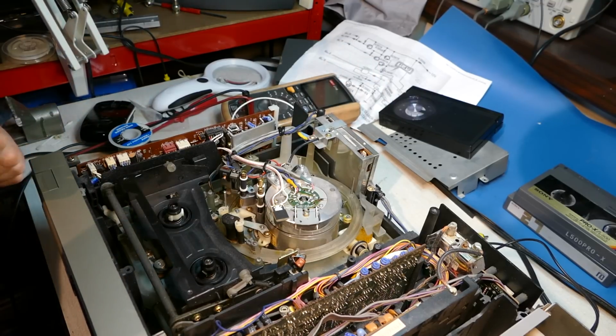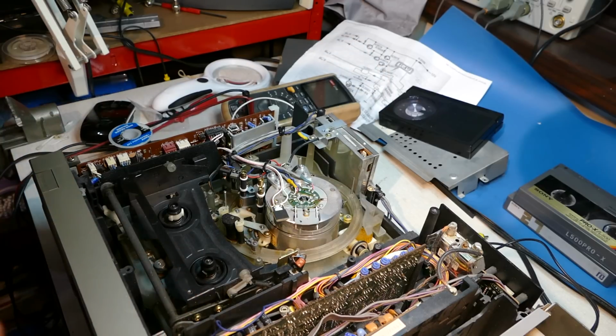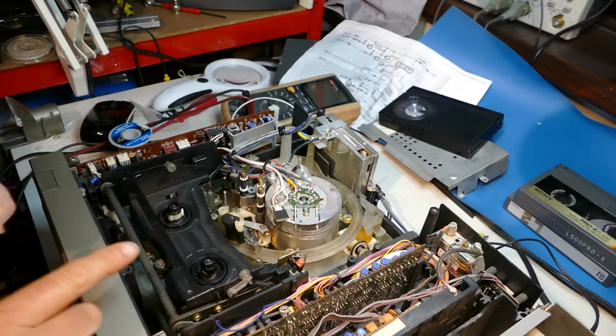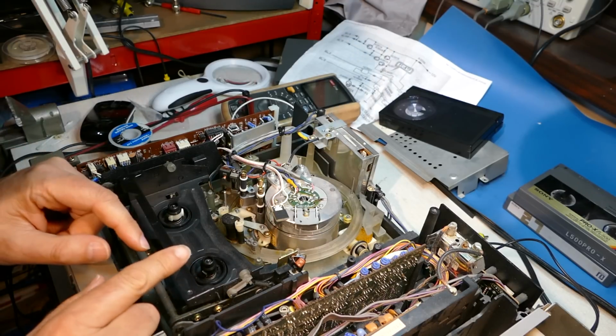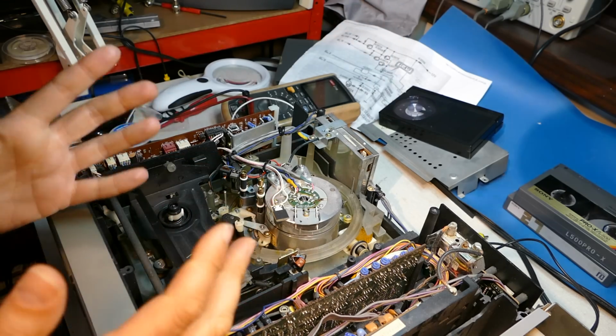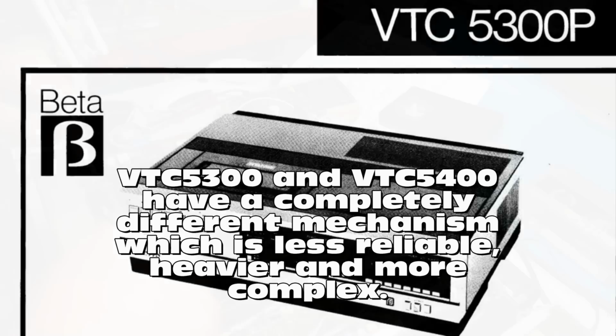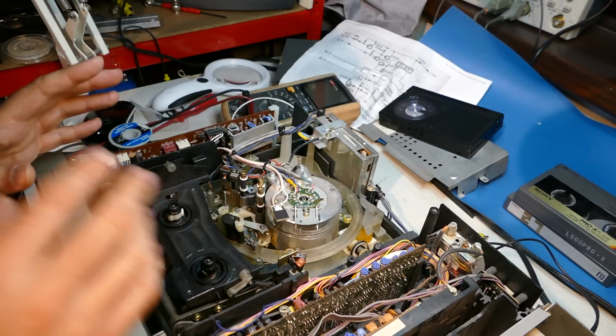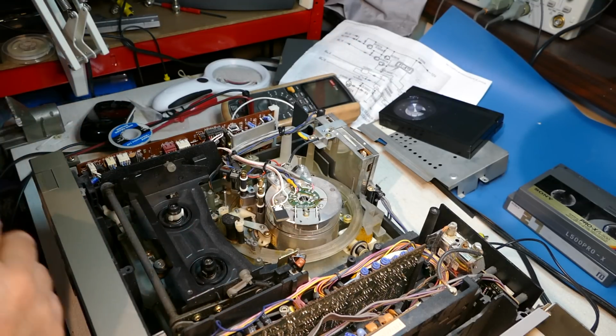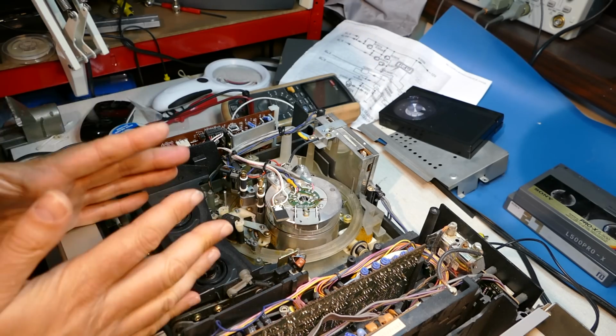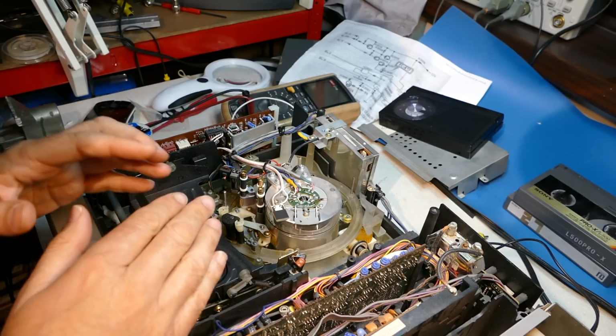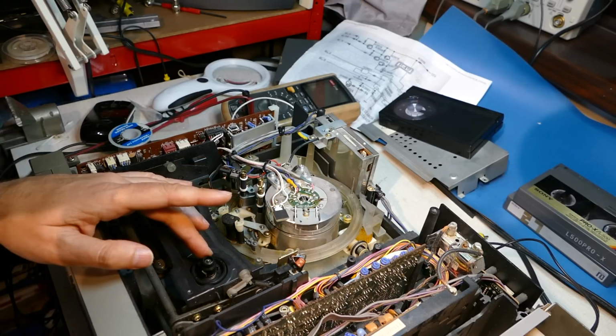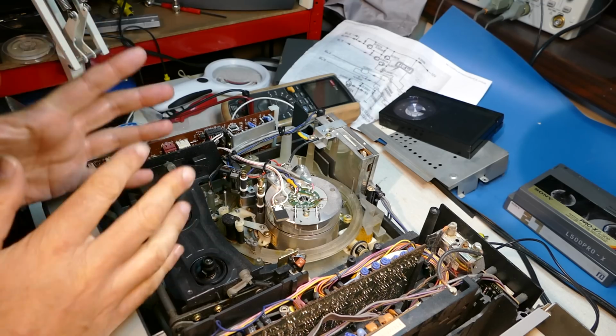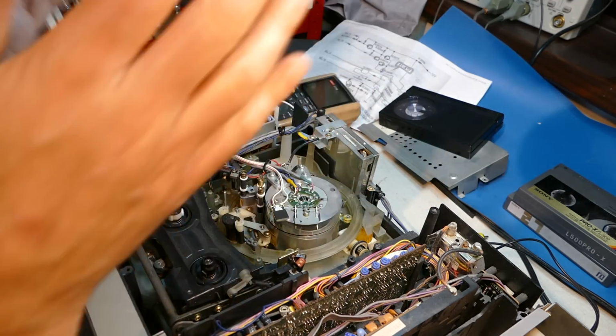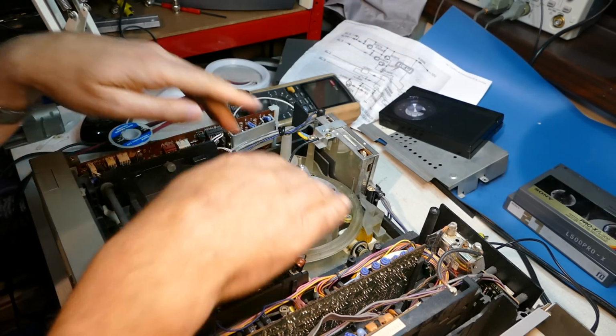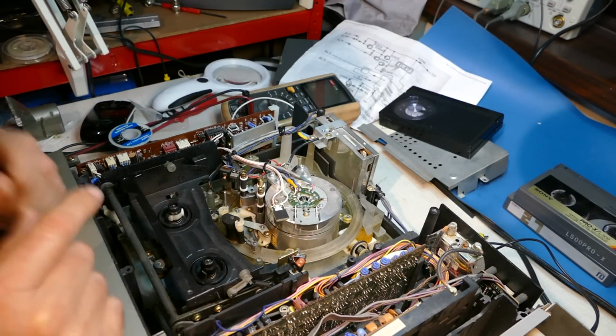Now I want to show you a bug. This applies to the VTC5000, and this is a 5150, so it applies to this too. I have a feeling they fixed it on some of the later VTC5150s. First, a bit of history: the model before the 5000 was, strangely, the 5300 and 5400, and those were always laced machines of the earlier type. I believe they copied some of the code from the Syscon, the system computer, into this machine and made a mistake. So when the machine gets into a fault condition and can't drive the reels, the 5300/5400 would go into its stop position, which is laced, stop. You don't want that in these models, because these do all their tape transport unlaced, but I think they left the lacing code in there.